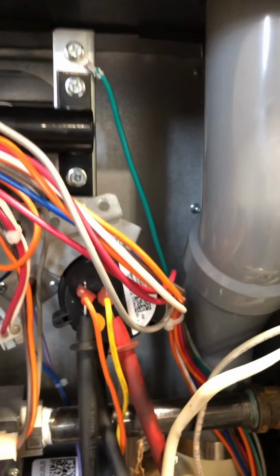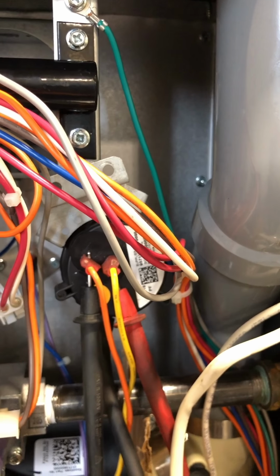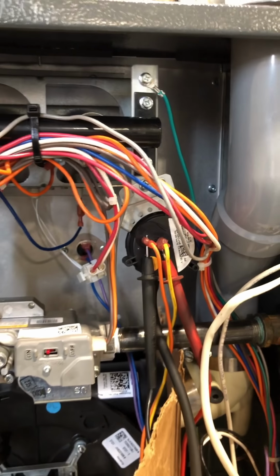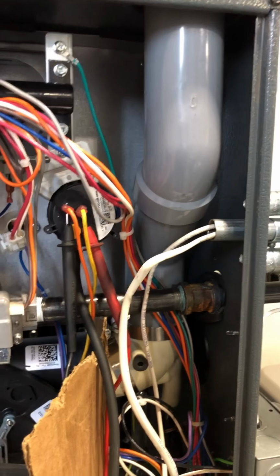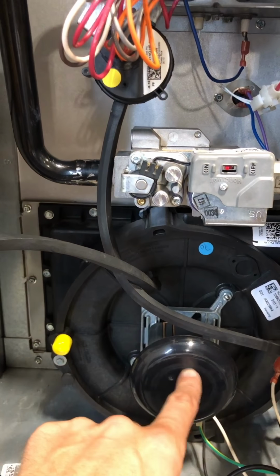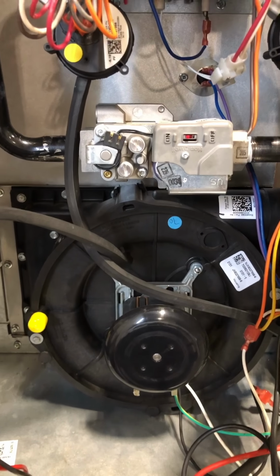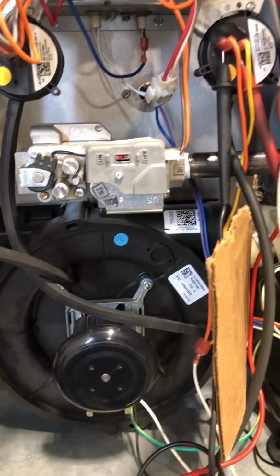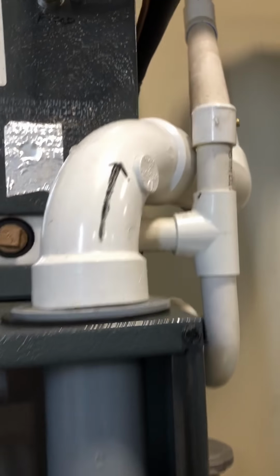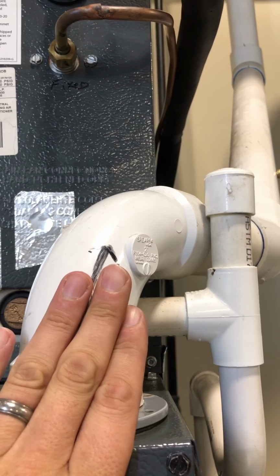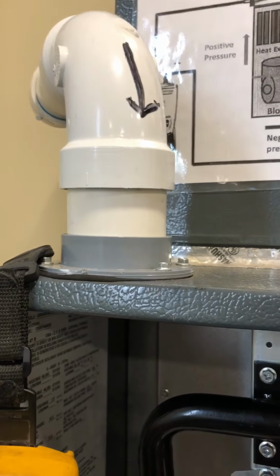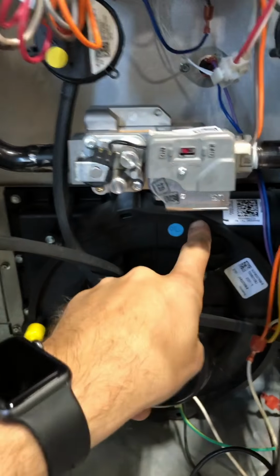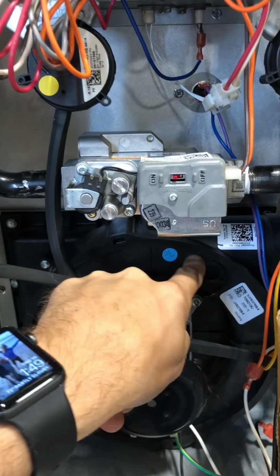So let's do a few tests here. Right now, like I said, I have my multimeter hooked across that switch. And a couple of things that will keep that switch from closing are, number one, our inducer motor flat just doesn't work. But number two, and usually more common, is we actually have a plug or something blocking either this exhaust pipe or this intake pipe, or something actually inside the inducer here that's blocking airflow from going.